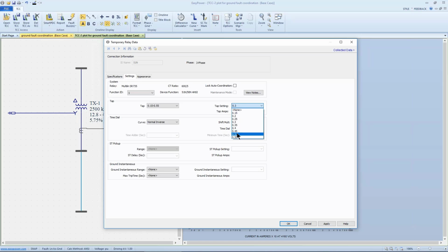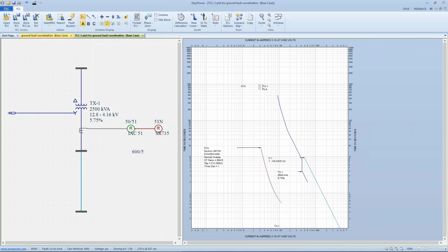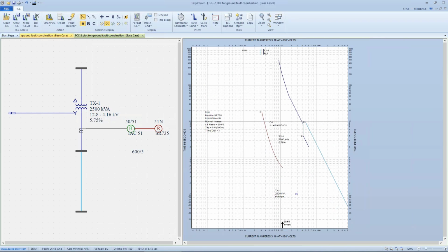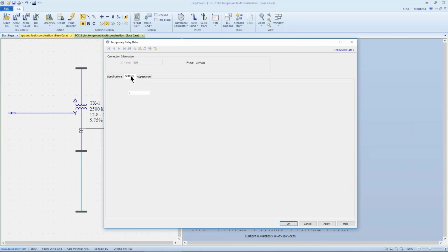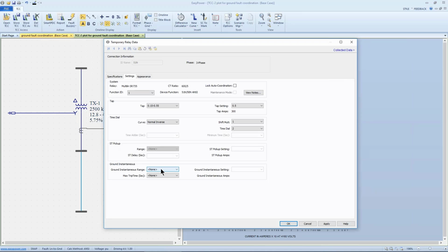I guess I can get there. And it could be adjusted with this little tab here at the top. So let's start off with 300 and see how it coordinates with everything else. All right, likewise, the time dial can be set after we realize what we're trying to protect. But for the most part, this is how long we're going to tolerate that particular level of current. So let's set it a little bit lower. And again, as we come back and look at our settings, we're not tolerating any instantaneous trip, in part because it interferes with coordination.